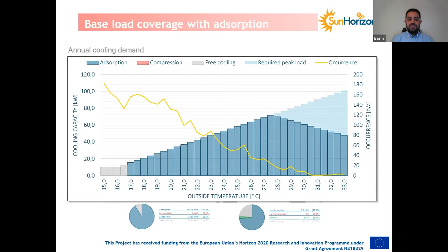So this backup system is recommended for absorption systems, and this is why we introduced our hybrid solution, the hybrid chiller. The hybrid chiller contains the absorption part, the absorption chiller, and also an integrated compression chiller that operates whenever required. So whenever we reach the peak load, or whenever there are fluctuations in the heat because of a lack of radiation or any other reasons, the compression part will automatically jump in and cover the missing cooling demand.